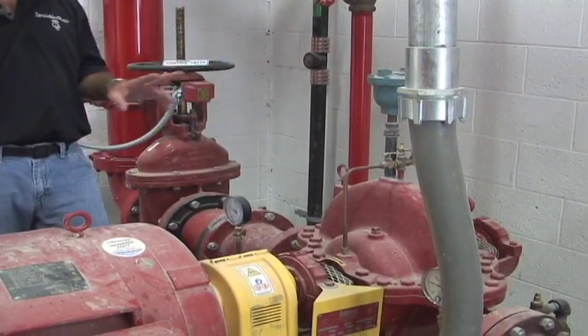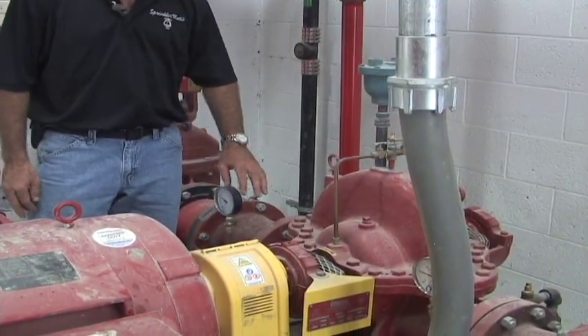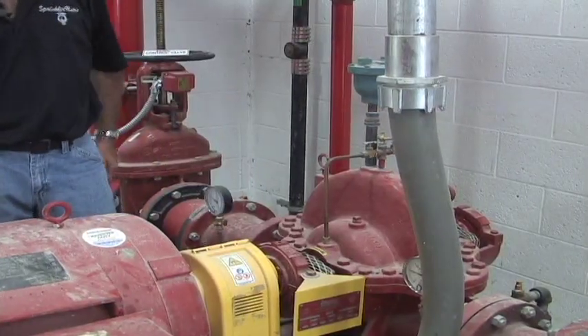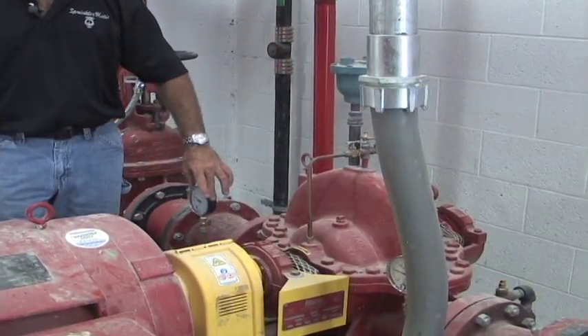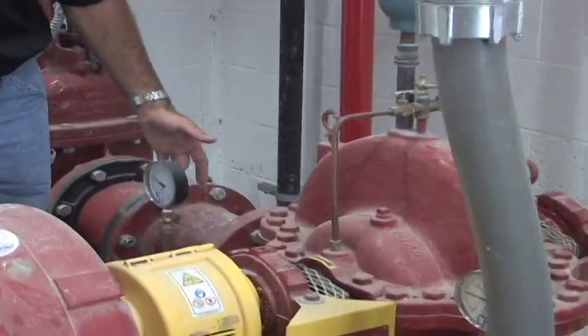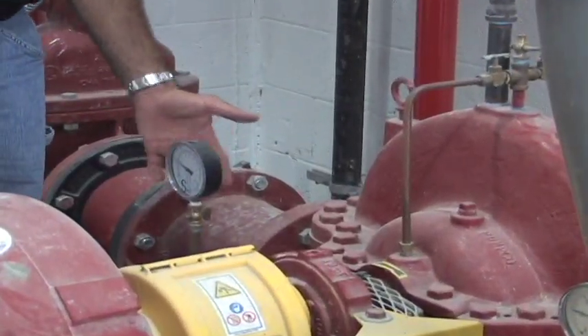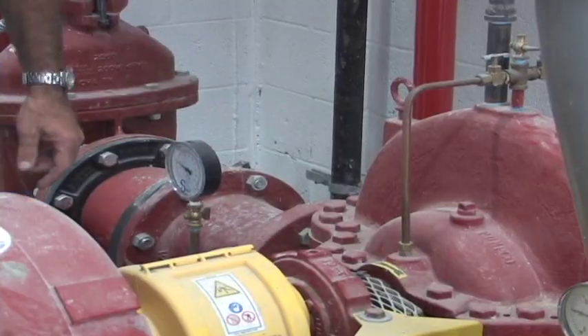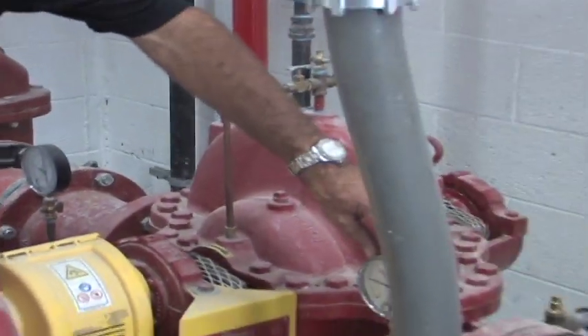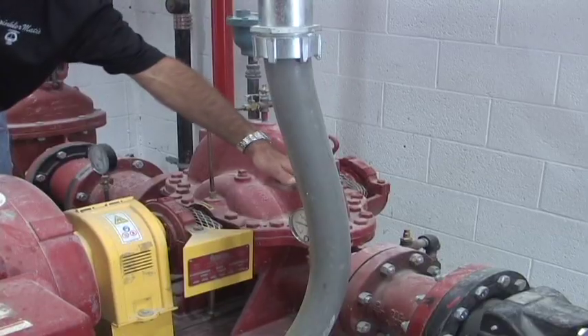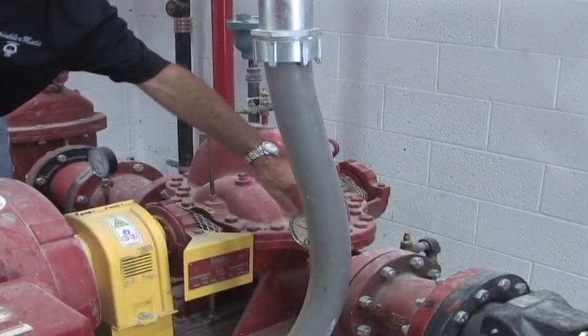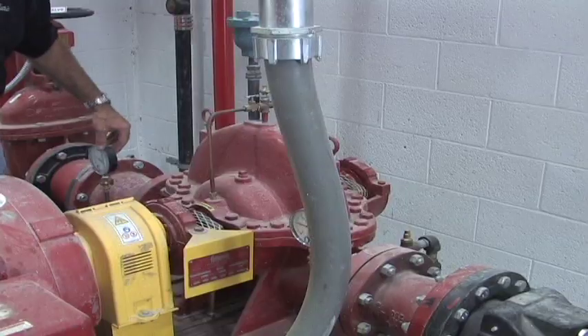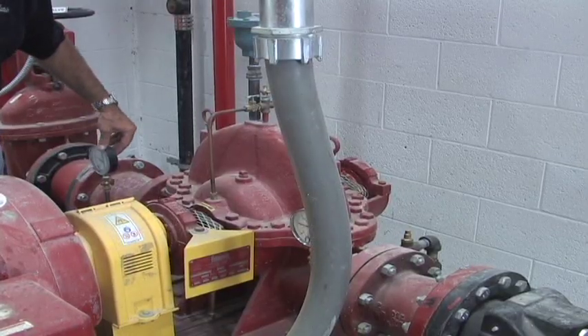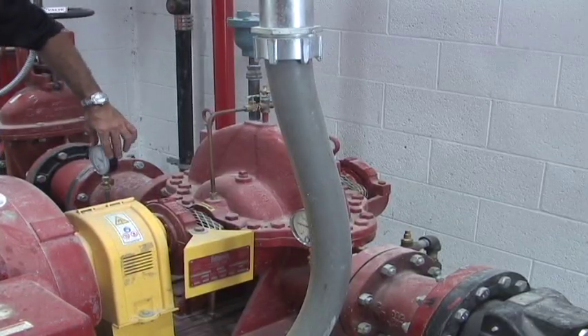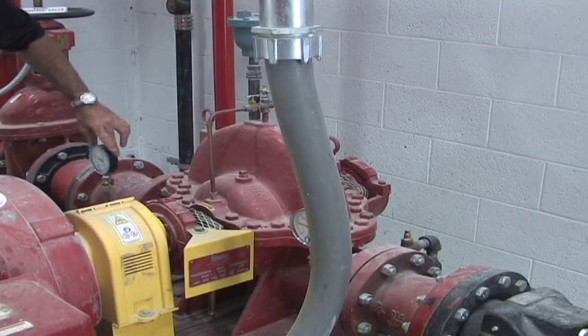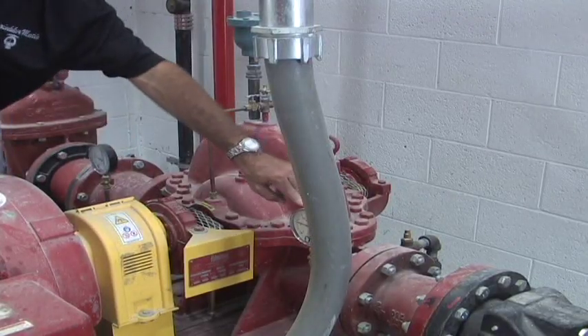All right, we have two sets of pressure gauges that we're going to look at throughout this whole presentation. We have our suction gauge, which is going to have us down to -30 if we started sucking the city water dry, up to 300 psi. Then also we have our discharge gauge. When the fire pump's on, whatever our discharge pressure, roughly about 190 psi, is going to go up in here. These two gauges are what we watch when we are running our pump for our weekly pump runs. These are the two numbers that we are going to write down on our sheet of paper showing what our supply is and what our discharge is.